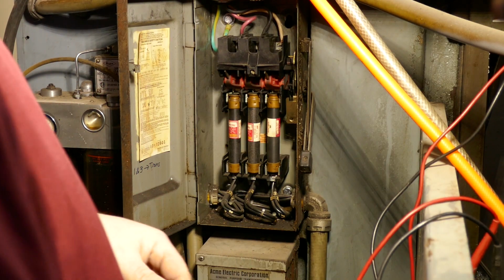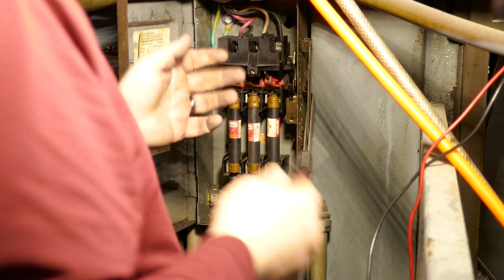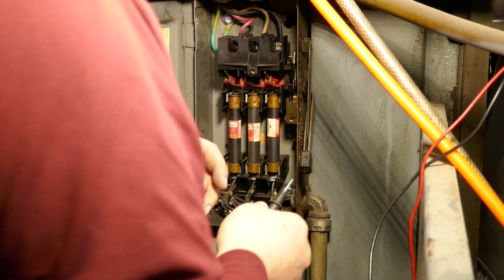Now I'm going to flip the black and white legs. Let's check our voltages: 111, 117, 198. Phase to phase on that is 223, phase to phase on that is 228, and phase to phase on that is 227. Awesome! So I'm between about 225 and 230 volts, somewhere around there.